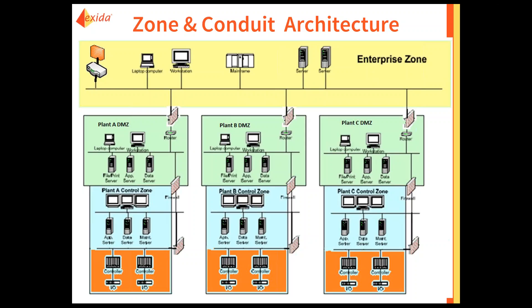The DMZs are commonly referred to as level 3.5 — a semi-trusted network. The DMZ is your connection point to allow traffic to flow from the enterprise to the DMZ, and from the control areas to the DMZ, but the enterprise is never allowed to communicate with the control area directly and vice versa. Below the DMZ we have an additional firewall communicating with the control zones in three plants. Our three servers — the app server, data server, and maintenance server — have lost their dual-NIC capability and must now communicate through the main control LAN down to the controllers. There is an additional firewall at this level.